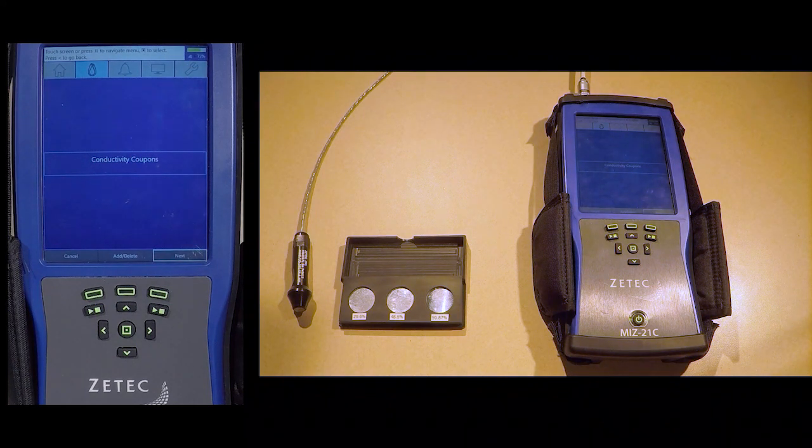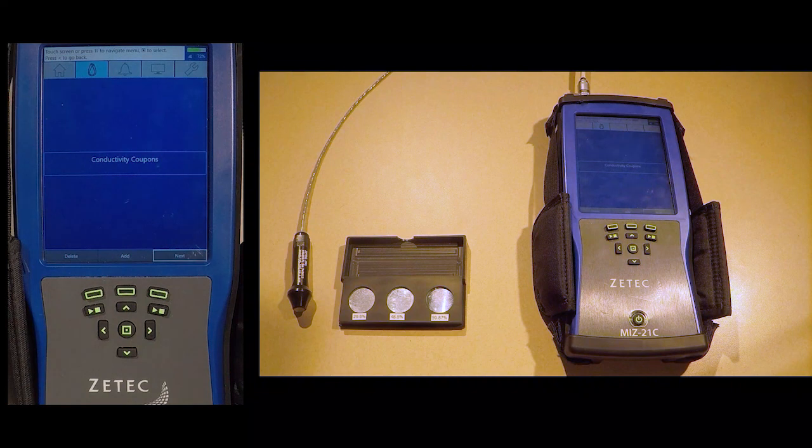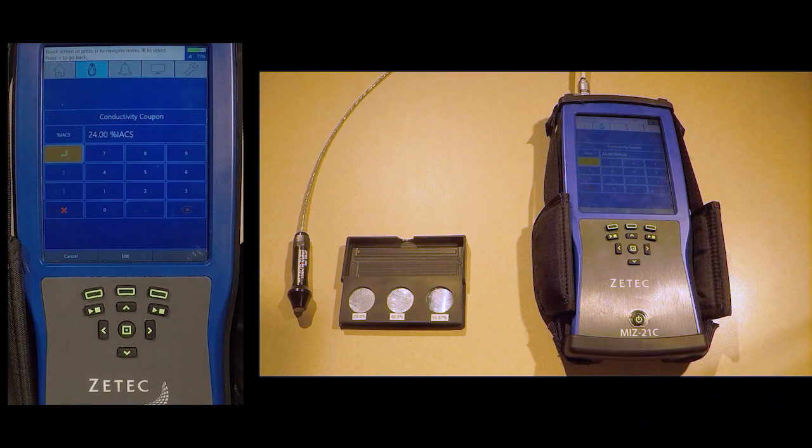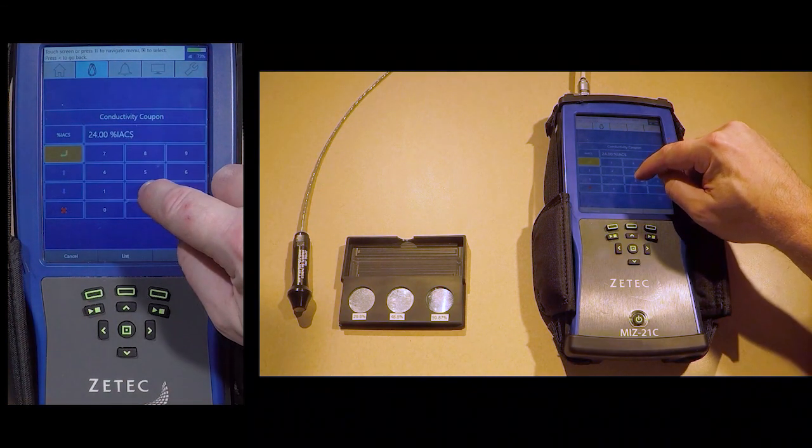The sample being used in this video has two values to be entered. Tap the Add-Delete menu item, then tap Add to enter the first coupon value. We will do this for both coupon values on the standard being used.